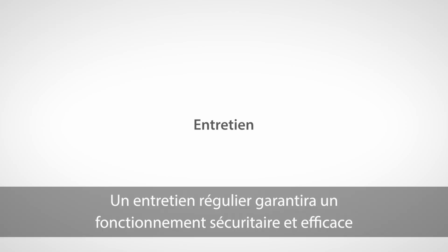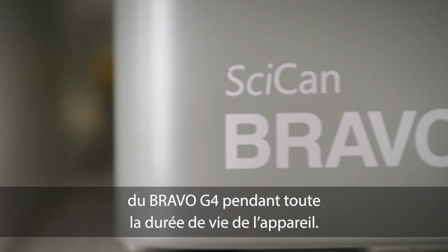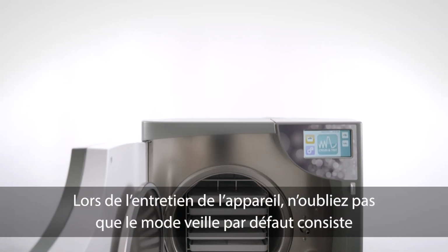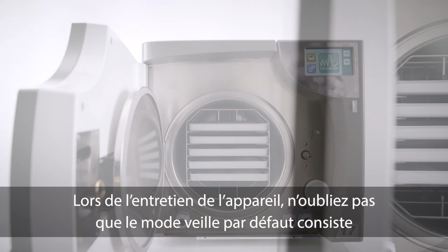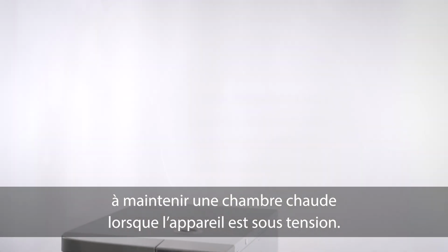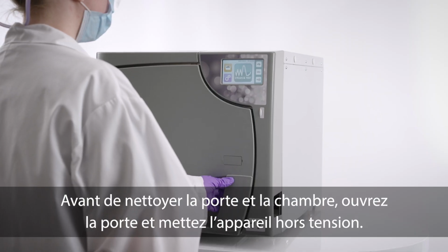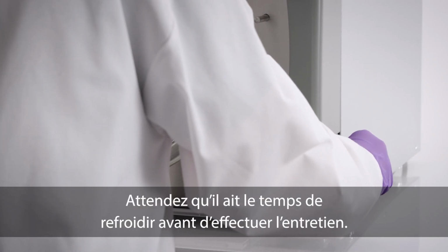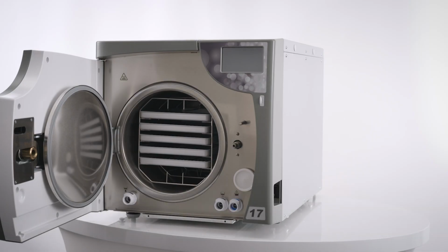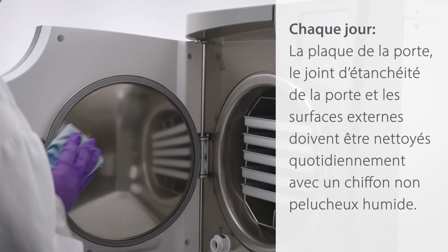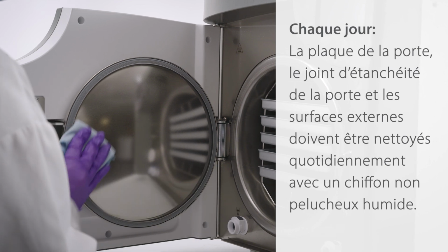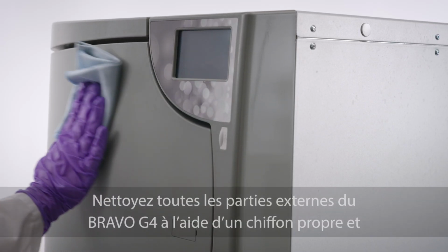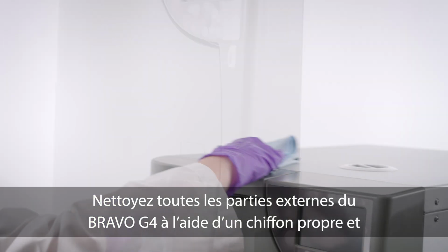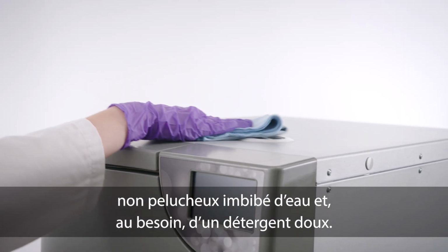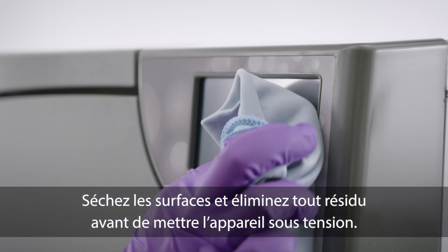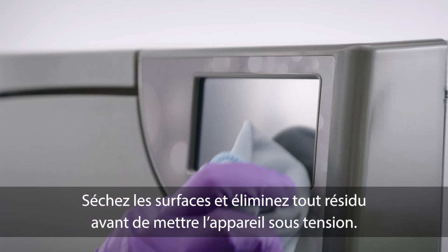Regular maintenance will help to ensure safe and efficient operation of the Bravo G4 over the device's life. When performing any maintenance on the unit, remember that the unit's default standby mode is to maintain a hot chamber while turned on. Before cleaning the door and chamber, open the door and turn the unit off. Allow adequate time to cool before performing maintenance. Daily. The door plate, door seal, and external surfaces should be cleaned daily with a damp, lint-free cloth. Clean all the Bravo G4's external parts using a clean, lint-free cloth dampened with water and, if needed, a mild detergent. Dry the surfaces and remove any residue before powering the unit on.